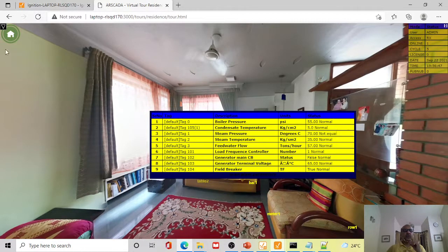So this refresh cycle is configurable. By default, it is refreshing at 5 seconds from the ARSCADA client to the ARSCADA server. It is basically an HTML page which, through AJAX calls, is receiving the tag values that are used in this. It doesn't request the entire database.